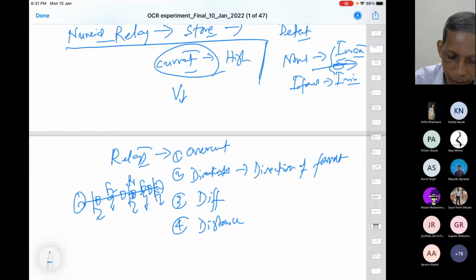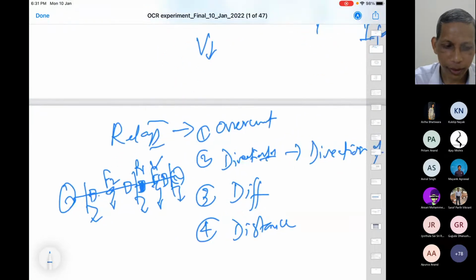So, this breaker I am hatching, this breaker should operate only for F1, not for F2. Only for F1, not for F2. Why? You see here, if this breaker opens for an F2 fault also, then this load cannot get energy or power from the right hand side at that time. So for an F2 fault, this breaker should not be operated. So the relay at R1 should have a discrimination capability.